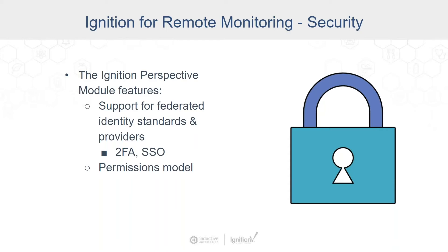The Ignition Perspective module has support for federated identity providers and standards. SAML 2.0 and OIDC are both supported in Ignition directly. These protocols let you use systems like Ping, Okta, Active Directory Federated Services, Duo, and a number of other identity providers. Federated identity providers often support features like single sign-on and two-factor authentication. In fact, at Inductive Automation, everything we do with Ignition or within our organization is protected by two-factor authentication wherever we can. So if you have other web apps using single sign-on, you can configure Ignition to use that same set, both for the apps and for the web browser visualizations, and it will tie into the rest of the infrastructure.